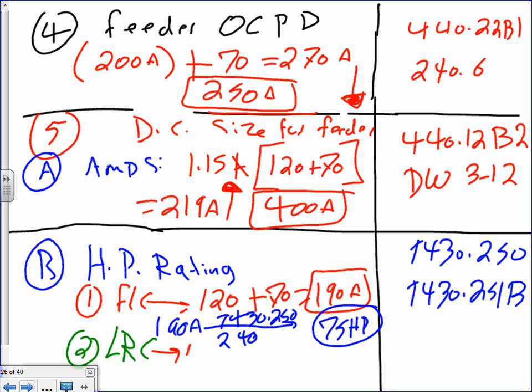For the locked rotor current, same thing, guys. I'm going to use green here for the locked rotor current. Let me just slow down here. Any question, guys? What I did, I added the full load amps, and I went to the table and sized based on the sum. The locked rotor current, the same way. You take 160 plus 451. That will get you a healthy 611 amp.